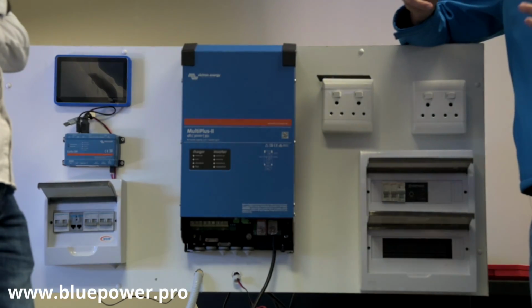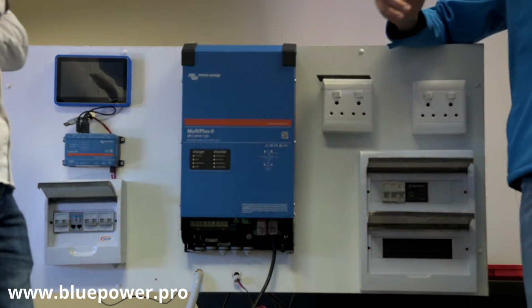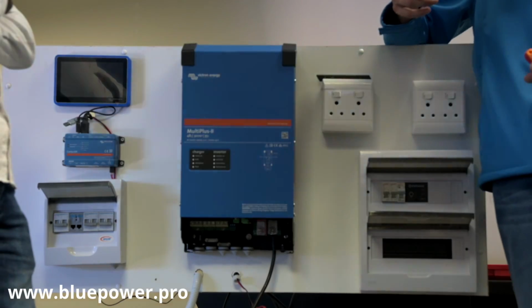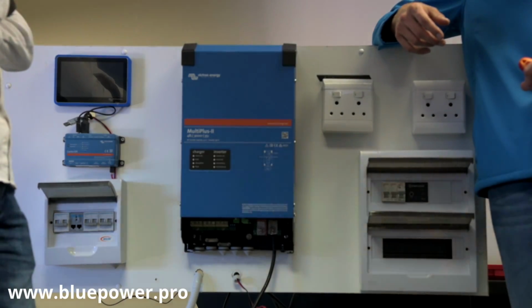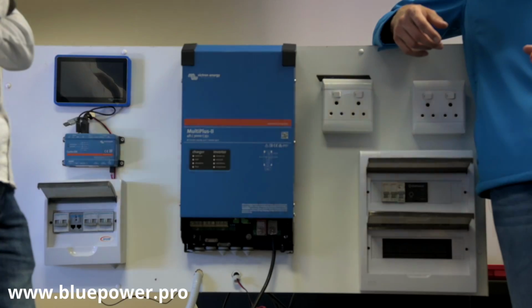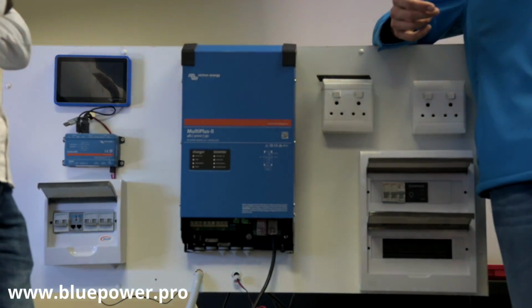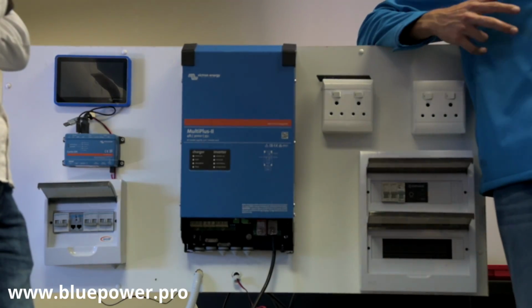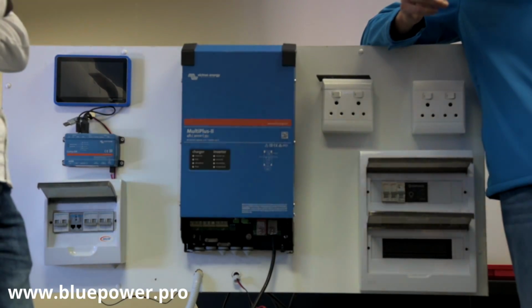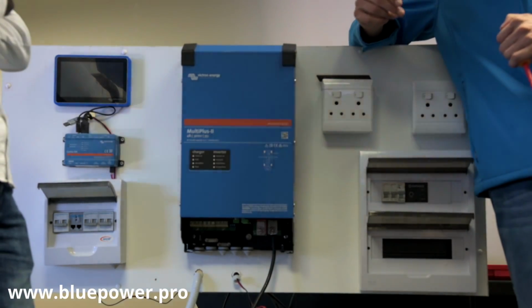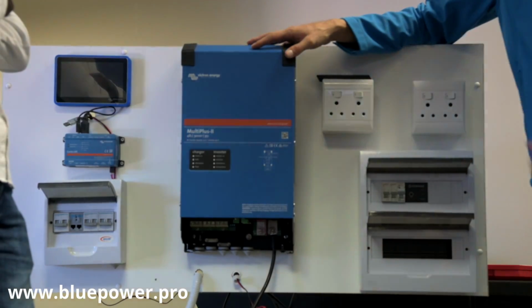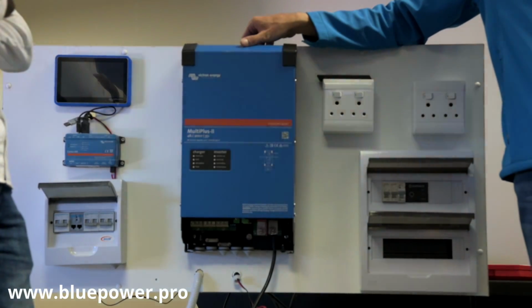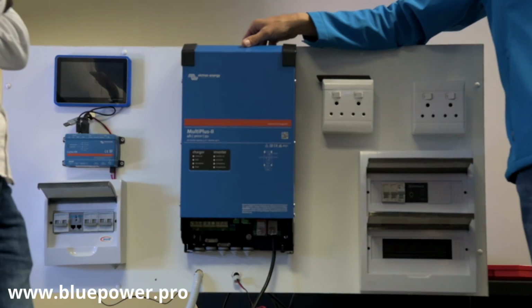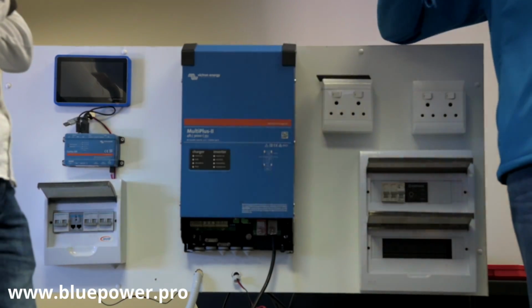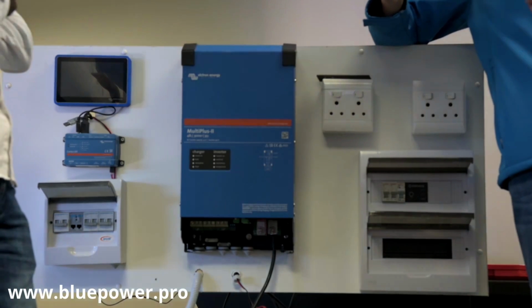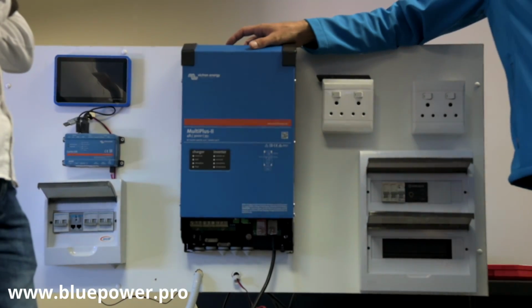That really depends on regulation, it varies a lot. I spoke to an electrical engineer and had it as positive only, and he said according to South African regulations you have to fuse both. But that's on the DC side, which is for PV, so it varies. We're not talking about regulations here, just recommendations - does it make any difference in terms of communication? You're going to struggle, because if you've got a blown fuse on one of the negative lines, the system isn't going to be able to recover.